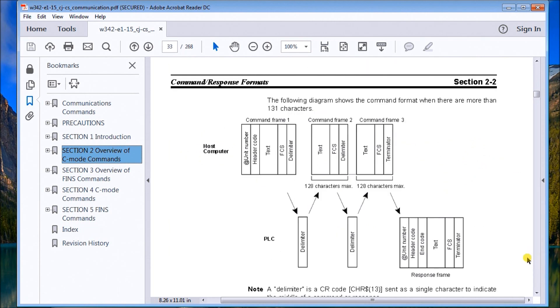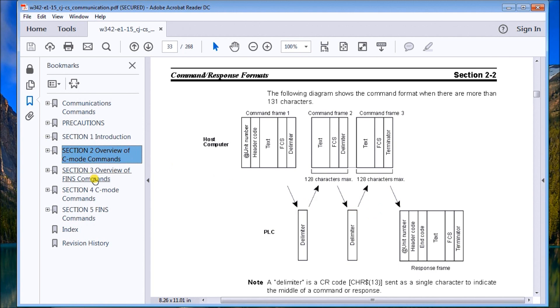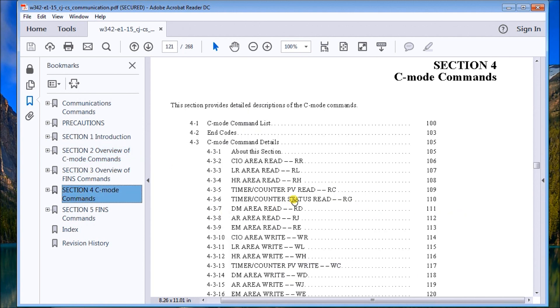Here's an example of the timing. We have our command, and if it's more than 131 characters we get a delimiter — just a carriage return without the asterisk. We then add another delimiter and it sends the next 128 characters. If still not at the end, we see another delimiter rather than a terminator, and it sends the next block. Finally we get a terminator and have the full message. This back-and-forth process handles multi-packet communication.